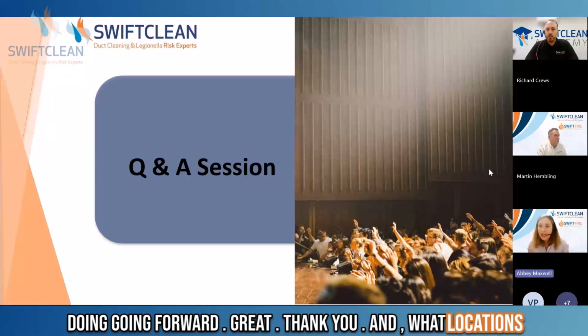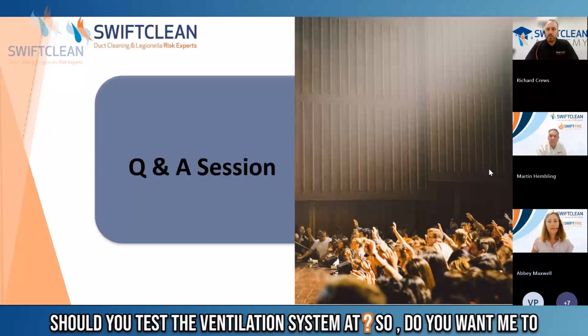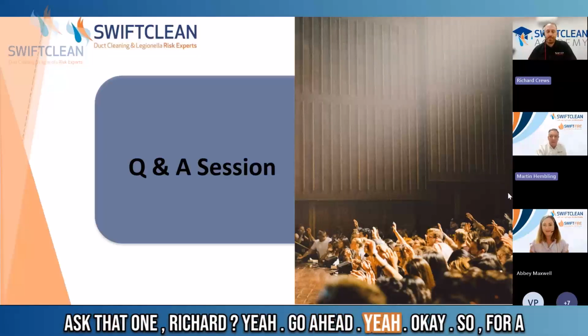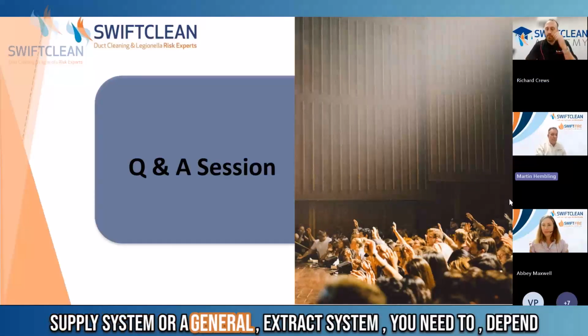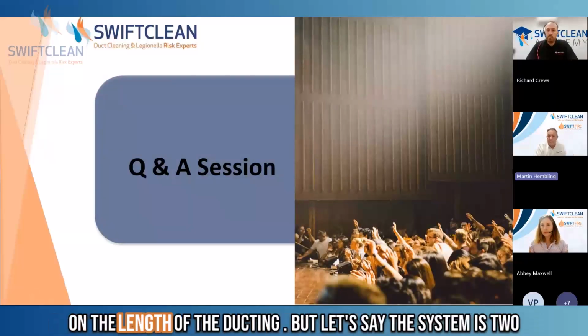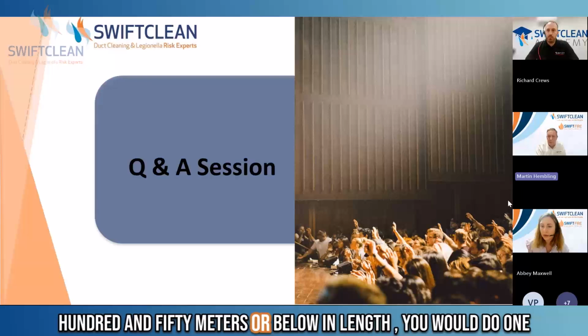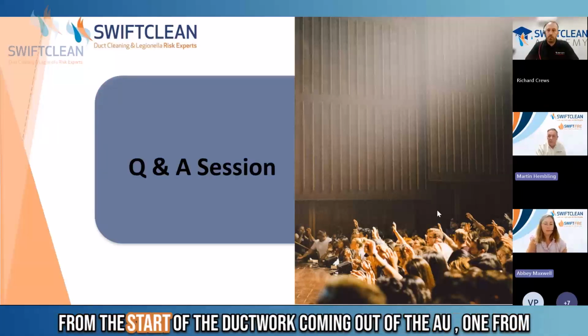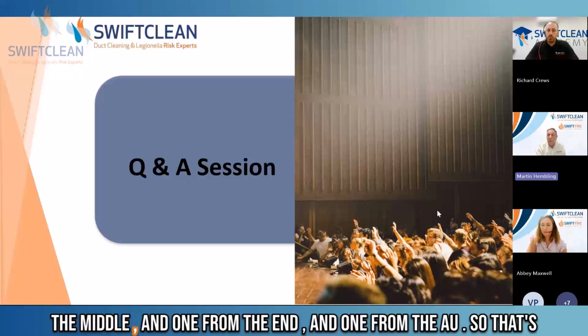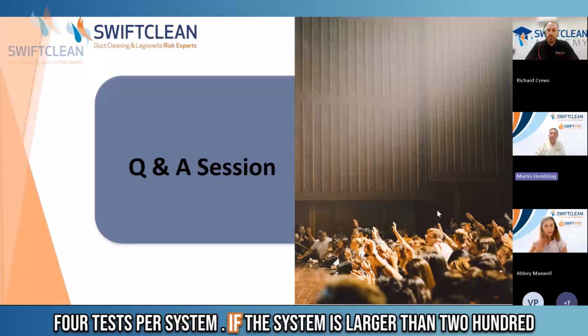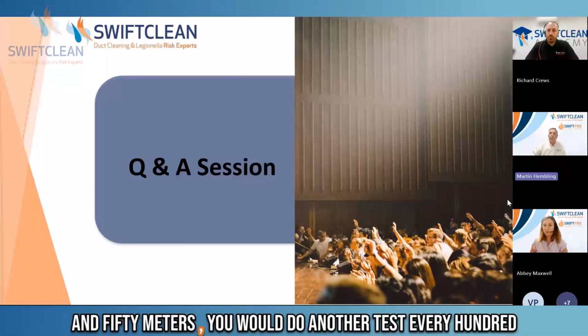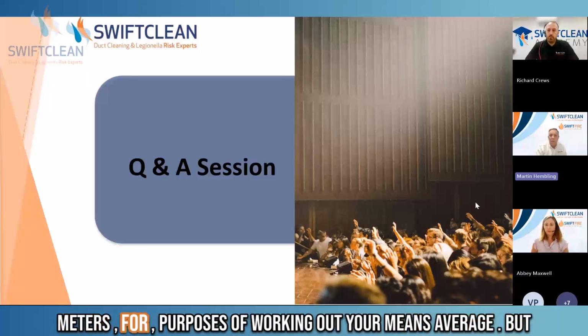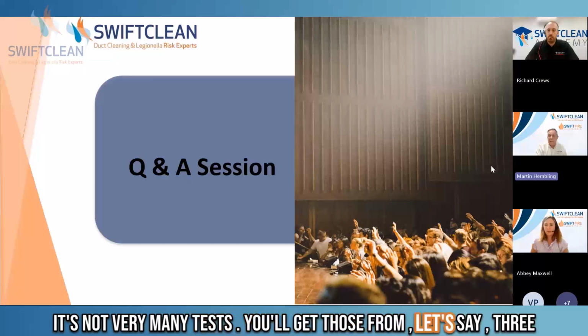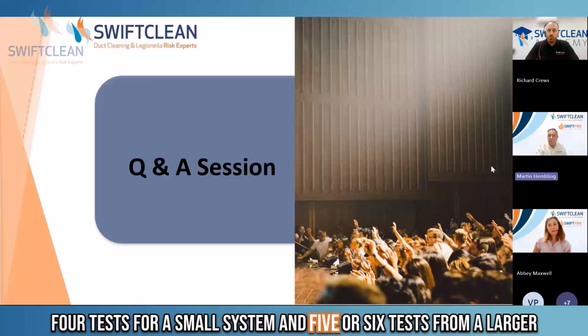What locations should you test the ventilation system at? For a supply system or general extract system, depending on the length of the ducting - let's say the system is 250 metres or below - you would test one from the start of the ductwork coming out of the AHU, one from the middle, one from the end, and one at the AHU itself, so that's 4 tests per system. If the system is larger than 250 metres, you'd do another test every 100 metres to work out your mean average. But it's not very many tests - you'll get 4 tests for a small system and 5 or 6 for a larger one.